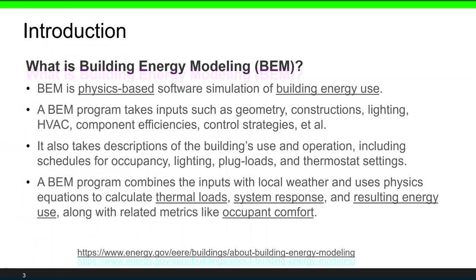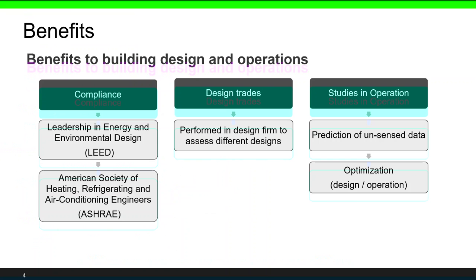What is building energy modeling? BEM is a physics-based software simulation of building energy use. A BEM program takes inputs such as geometry, construction, lighting, HVAC (heating, ventilation, and air conditioning) component efficiency, control strategy, etc. It also takes descriptions of the building use and operation, including schedules for occupancy, lighting, plug loads, and thermostat settings. A BEM program combines these inputs with local weather and uses physical equations to calculate thermal loads, system response, and resulting energy use, along with related metrics such as occupant thermal comfort.